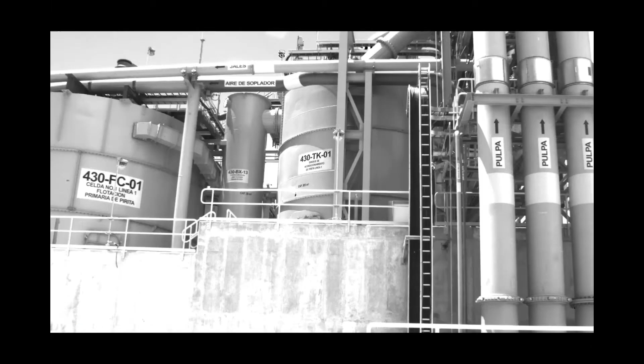And that's the idea. In this case, this was Gold Corp in Mexico. They used the camera for commissioning, during installation and then ultimately the commissioning. They caught this, and the way they leveraged it is they tied the camera to acceptance criteria. So in addition to troubleshooting for root cause, we always encourage people to use the camera whenever you do a new installation, and make sure you look at it before the installer has left.